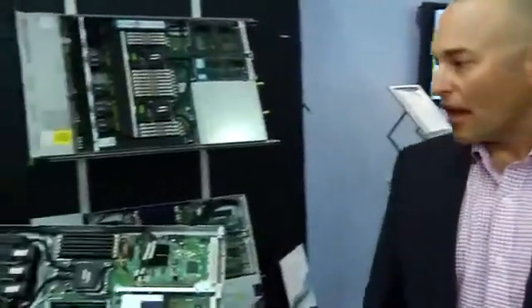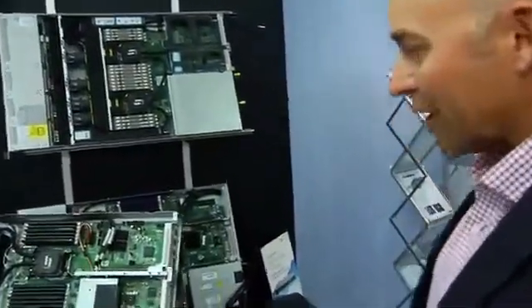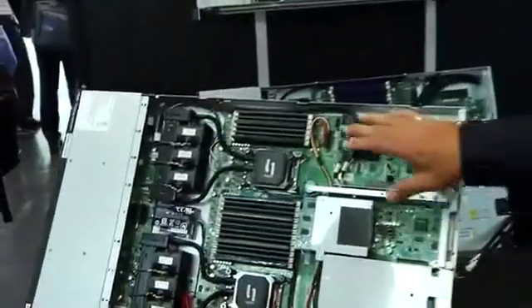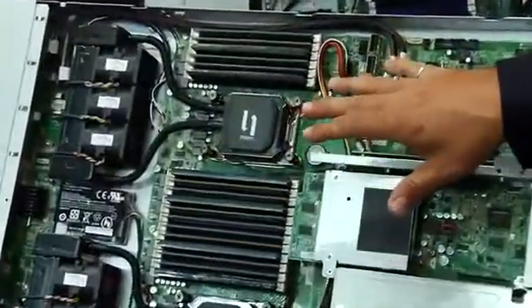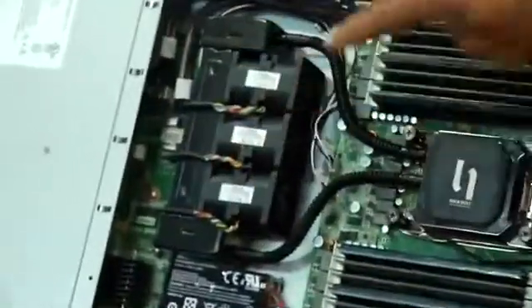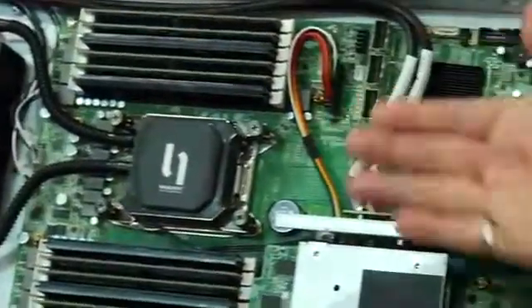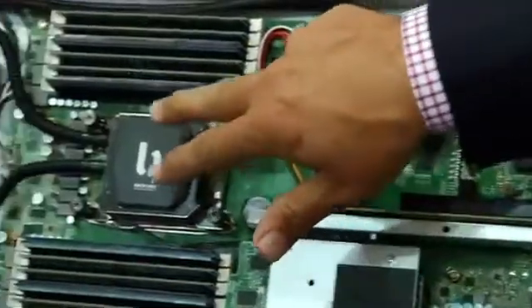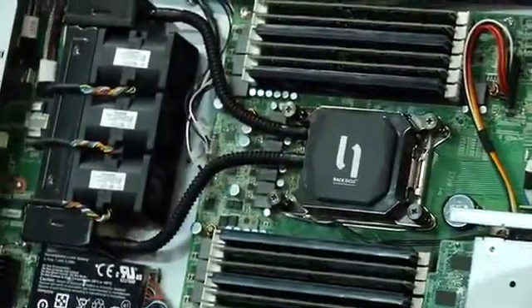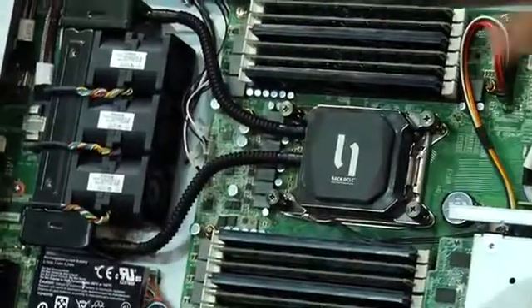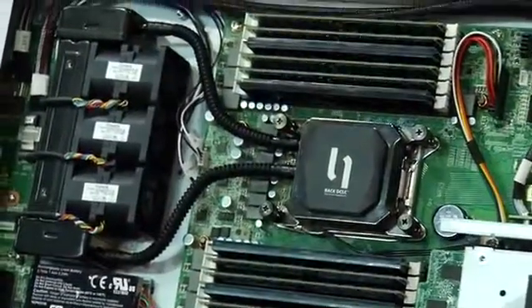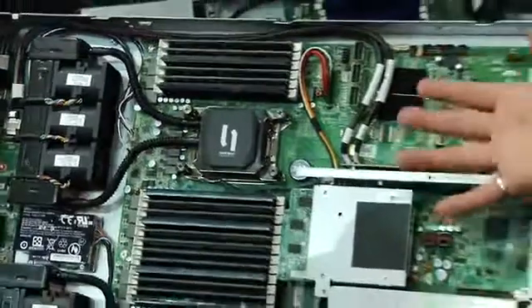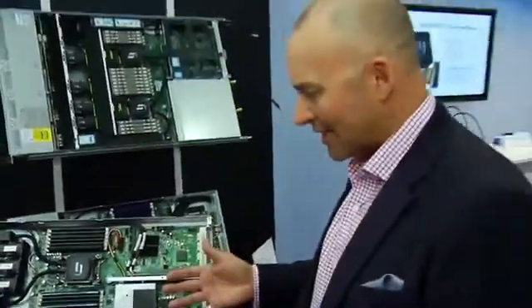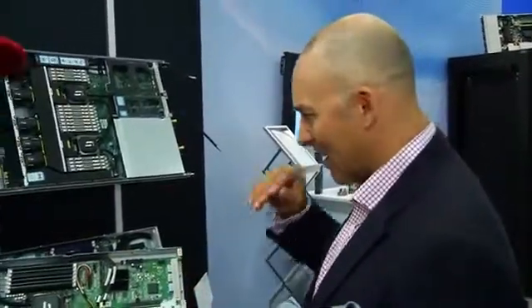So what do we got here? What are you showing off? We've got a variety of solutions we're showcasing here at ISC. The first is a closed-loop solution, with a radiator built right into the server. The benefit is being able to support a higher-powered CPU, or potentially reduce the fan power used inside the server. If it comes right down to it, it's just a better heat sink, in order to think of it at that scale.